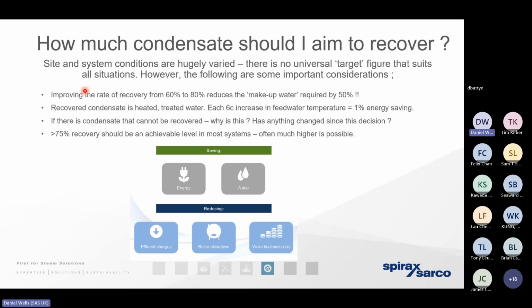And the next question our client asks us is, is that good? Is that bad? Well, we don't know, because we don't really know what our client is using their steam for unless we've had the benefit of walking their plant to become familiar with their processes. If our client's got a significant number of direct steam usage points, if they've got a lot of humidification, or if they're heating up a lot of tanks through direct steam injection, then, as we've mentioned previously, there isn't going to be that opportunity to recover any more condensate. If they've got 100% indirect heat exchange systems, then we'd like to think that we could recover all of that condensate.